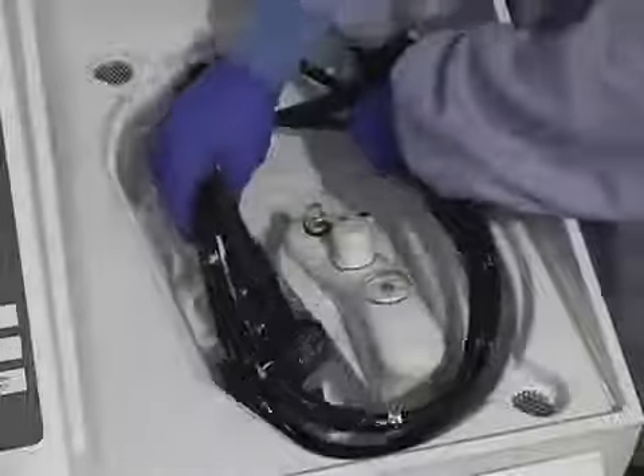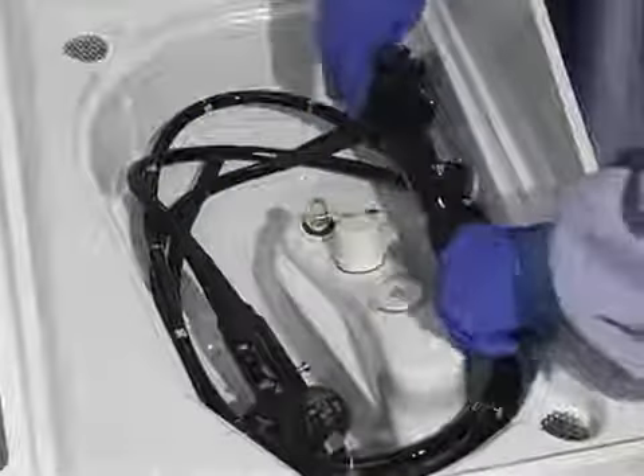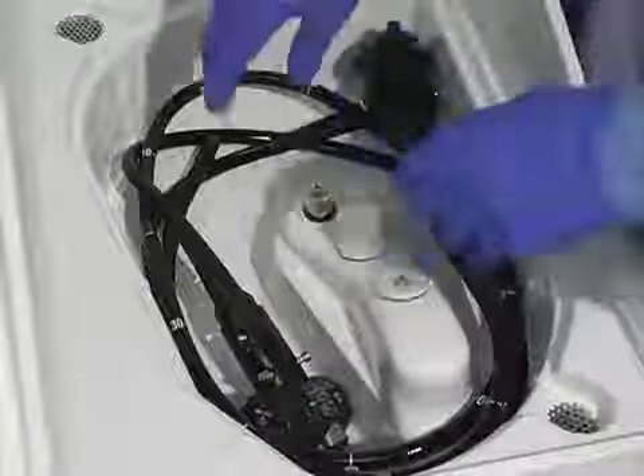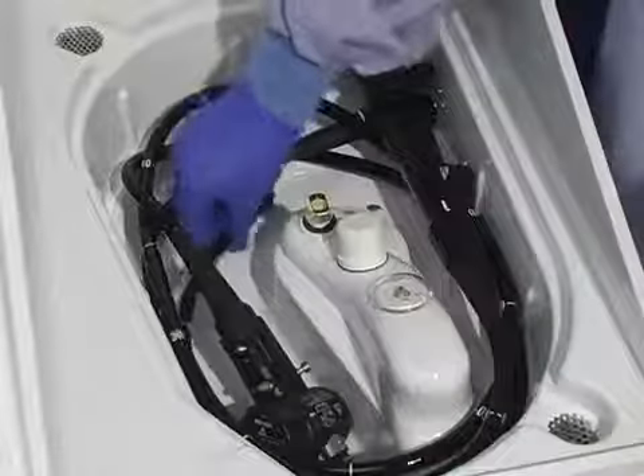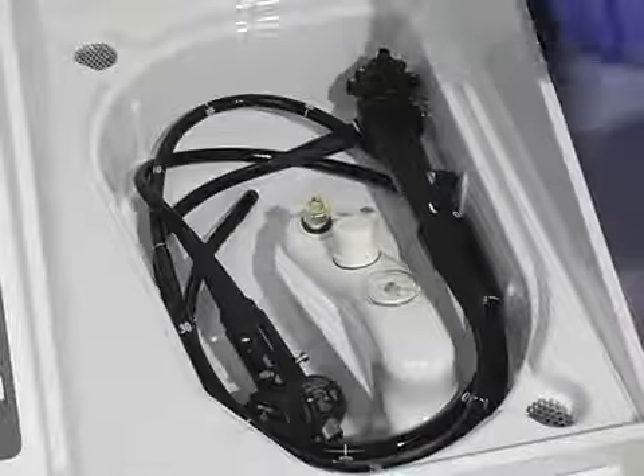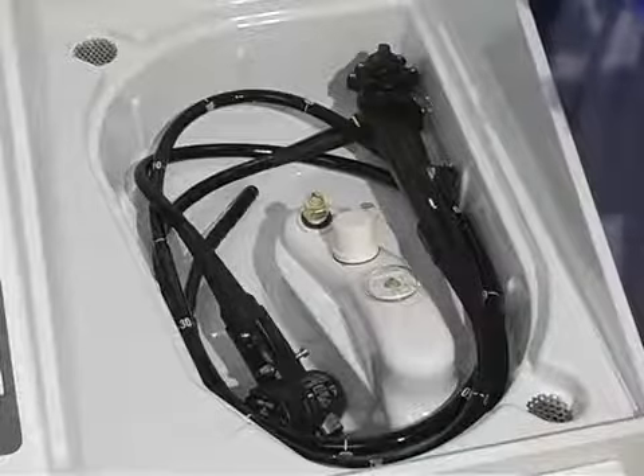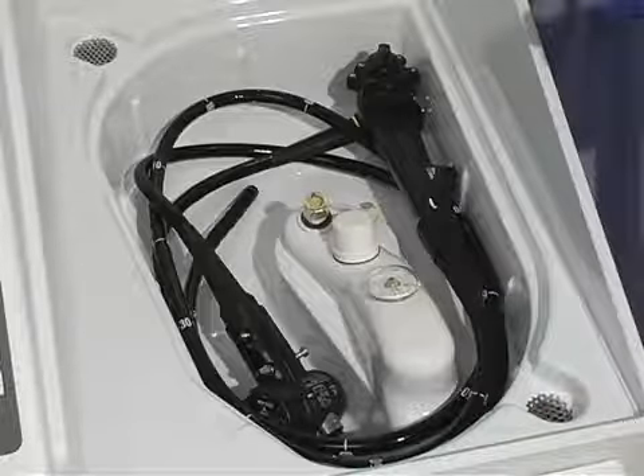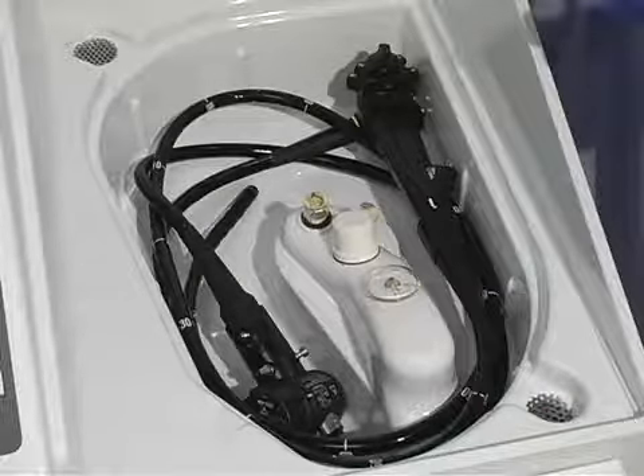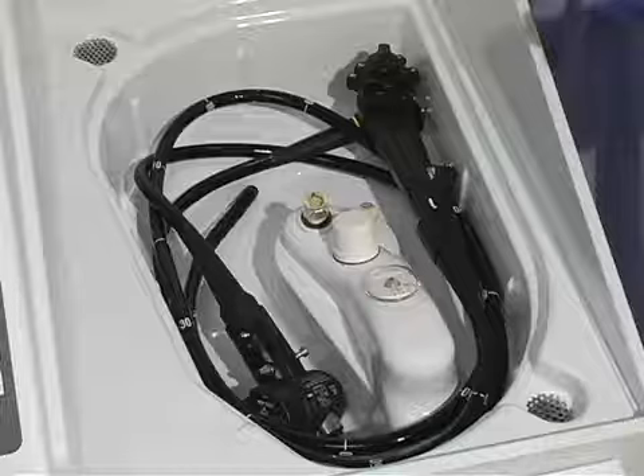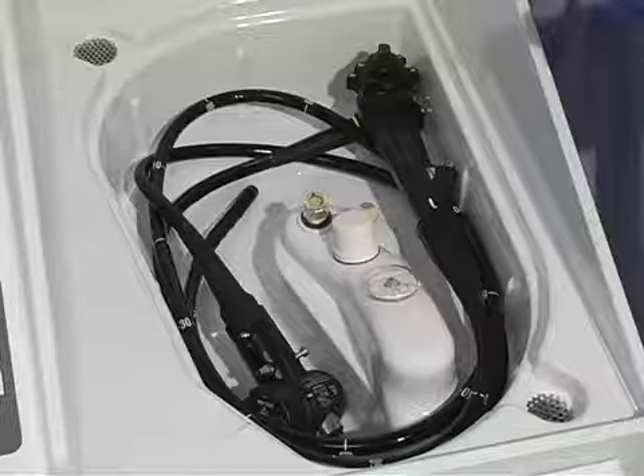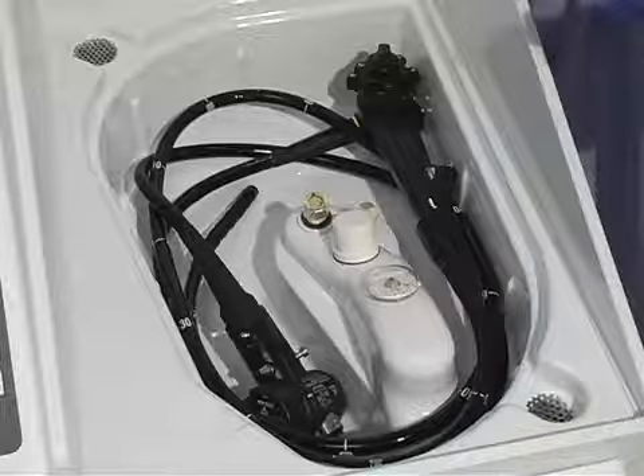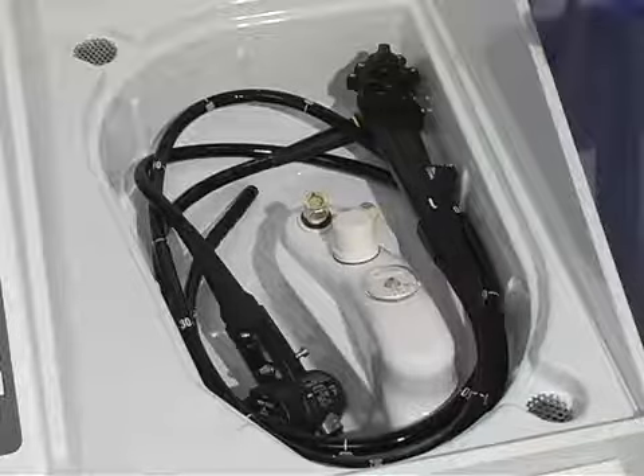Pre-coil the endoscope before placing it inside the basin. Hold the endoscope by the control section. Loop the light guide cable so that the light guide connector hangs about 1 foot below the control section. Loop the endoscope insertion tube in a similar way. Place the control section at the right rear of the basin and the light guide connector at the left front.